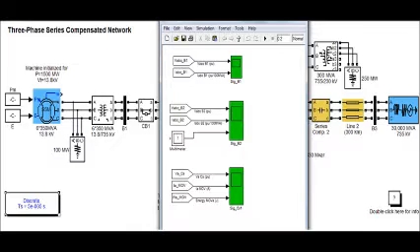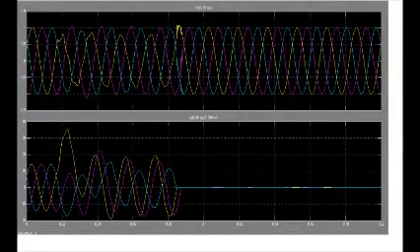The series compensation subsystems are identical for the two lines. For each line, each phase of the series compensation module contains the series capacitor, a metal oxide varistor MOV protecting the capacitor, and a parallel gap protecting the MOV. When the energy dissipated in the MOV exceeds a threshold level of 30 MJ, the gap simulated by the circuit breaker is fired. CB1 and CB2 are the two line circuit breakers.